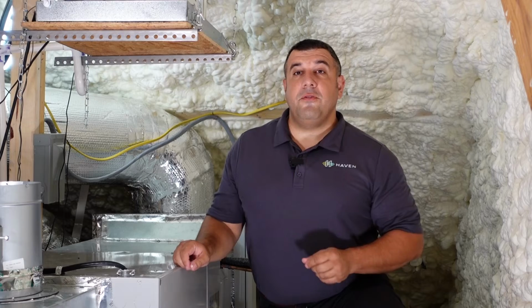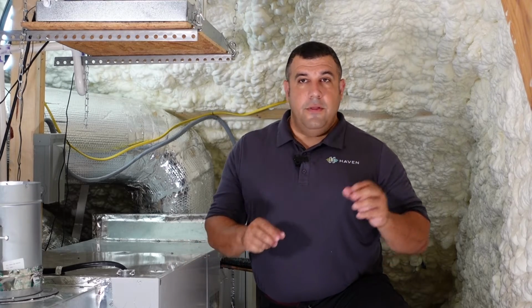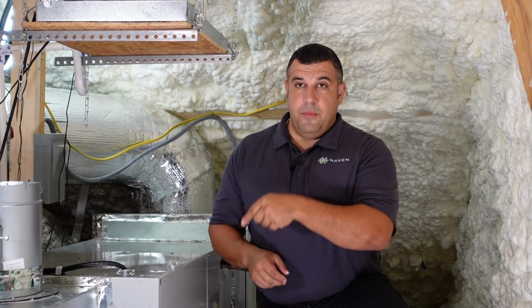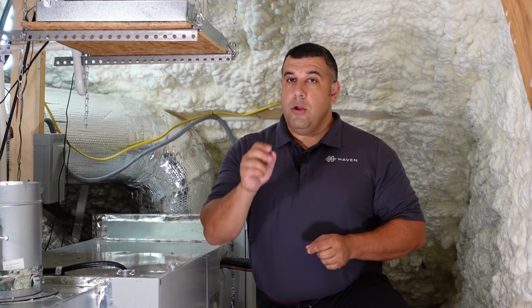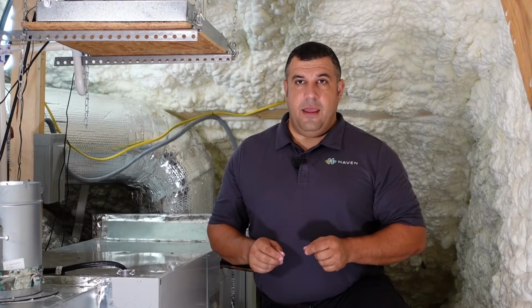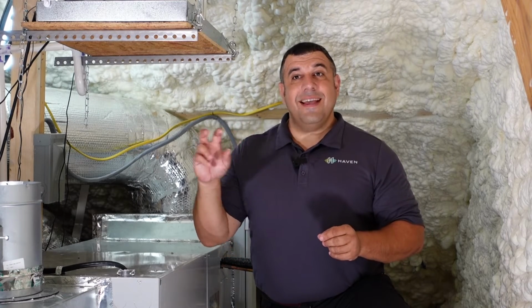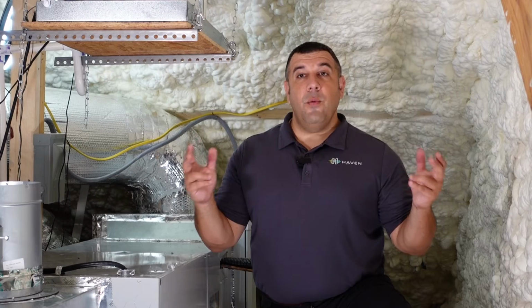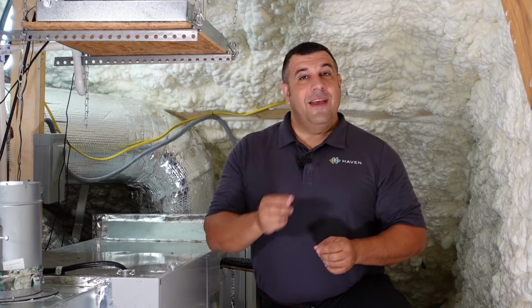You'll have a couple of options for powering the monitor, either off the R and C terminals from the air handler control board or using a dedicated power supply. For this, you can install a secondary 24 volt inline transformer or use a wall plug transformer. The monitor can accept anywhere from 9 to 30 volts AC or DC.